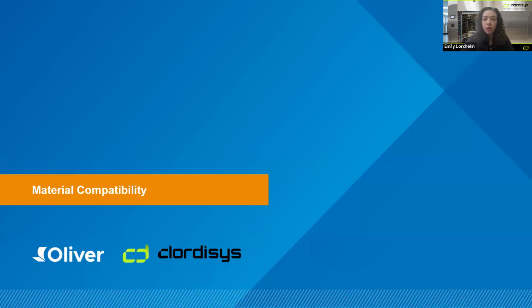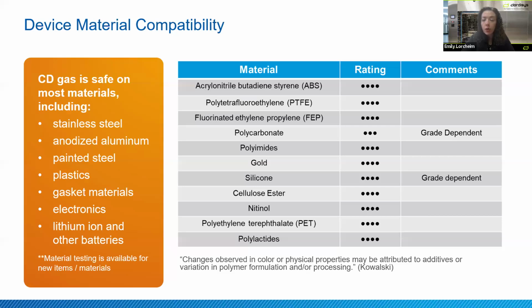So we're going to talk about material compatibility again briefly. We can provide extra studies if anybody wants more information, but we'll give a brief overview here. So chlorine dioxide also has been added to AAMI TIR 17, which is the compatibility of materials subject to sterilization. But it's just to give an overview, it's compatible with most materials. So stainless steel, anodized aluminum, plastics, polymers of any type. Now, there are some things where different additives may cause some yellowing, potentially some polycarbonates with bromine additives, and so forth. And with any sterilization modality, you will want to test your device with the sterilant because anything can be, not cookie cutter with that.